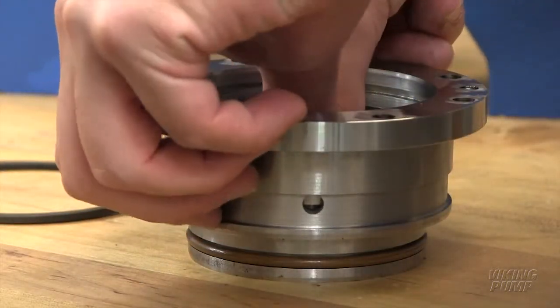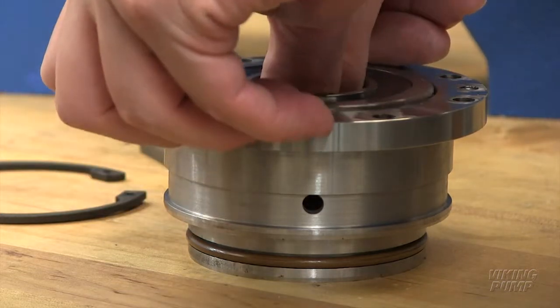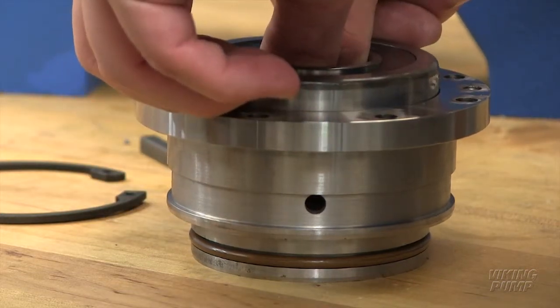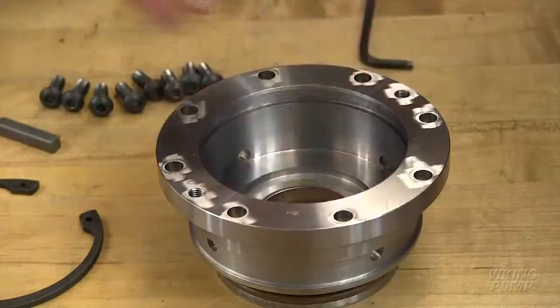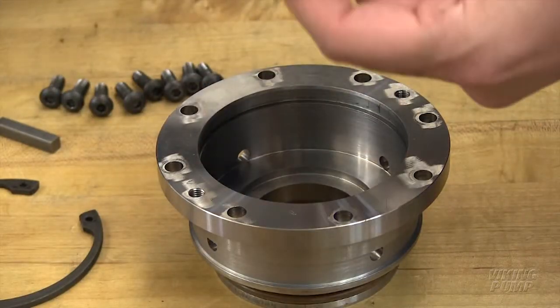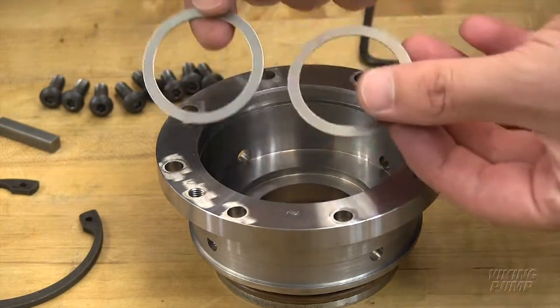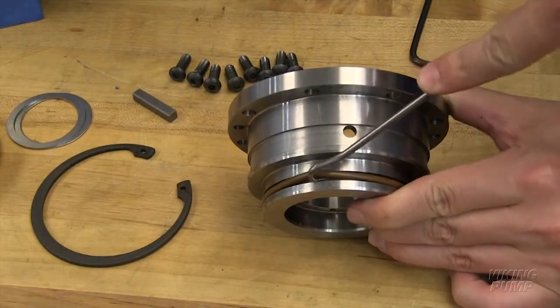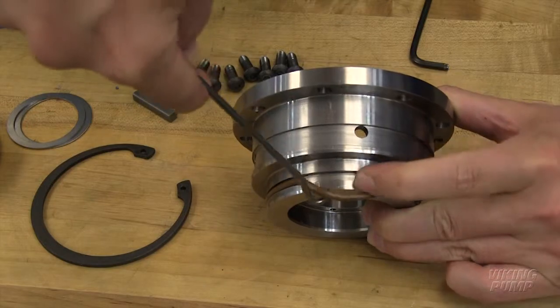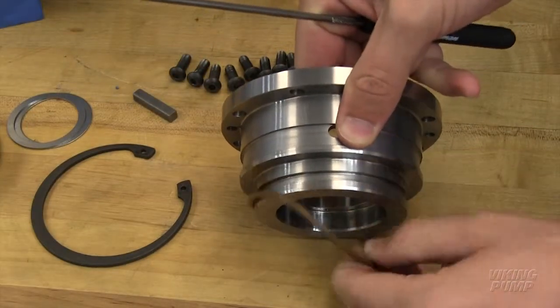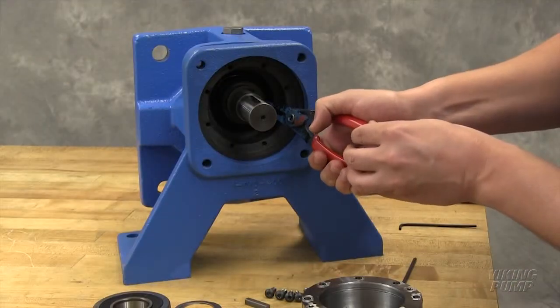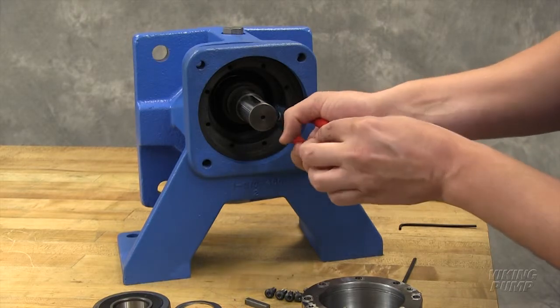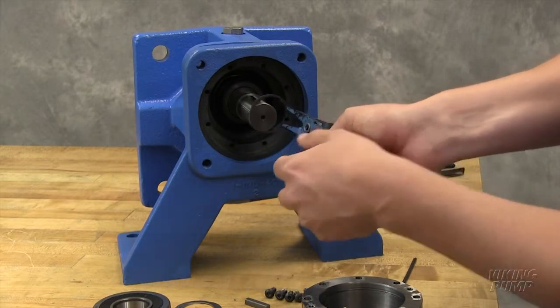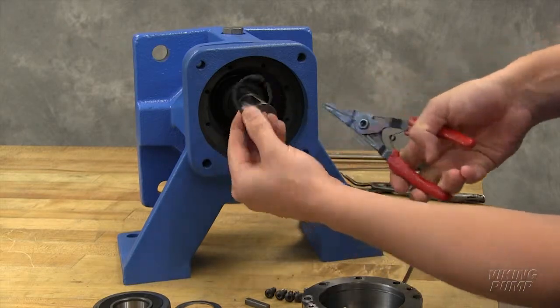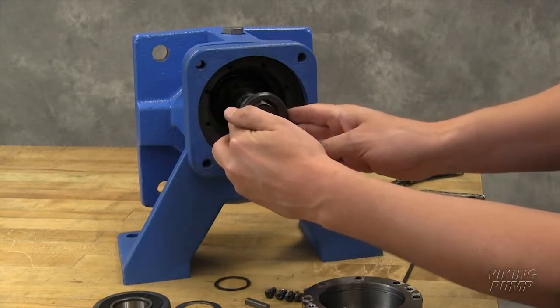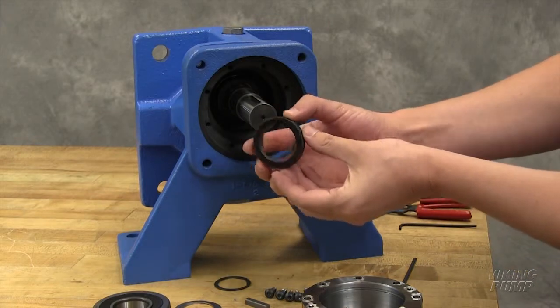Remove the ball bearing from the seal holder. Remove the bearing shims. Remove the O-ring from the outside diameter of the seal holder. Use the snap ring pliers to remove the retaining ring on the shaft that locates the thrust bearing. With the retaining ring removed, the stationary seat can be removed from the assembly.